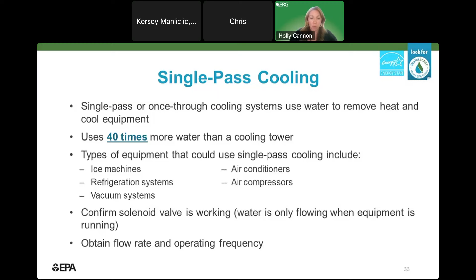It's commonly used for ice machines, medical and laboratory equipment, vacuum systems, and air compressors, and often the flow of water could be controlled by a solenoid valve, so it's only flowing when that motor or compressor is running. But in older models or cases where that valve fails, which is very common, water could be flowing continuously. If you do see it, make sure you obtain the flow rate and the frequency. It's definitely best to recommend replacing single pass cooled equipment first and foremost with air cooled equipment, or also potentially recommending that they use an existing chilled water loop or their cooling tower for cooling.